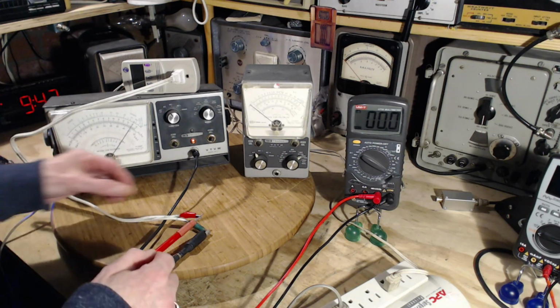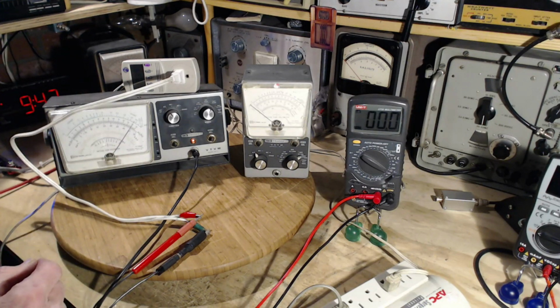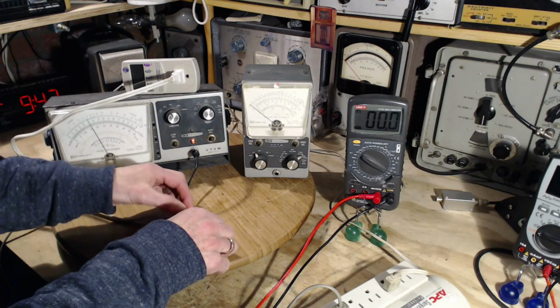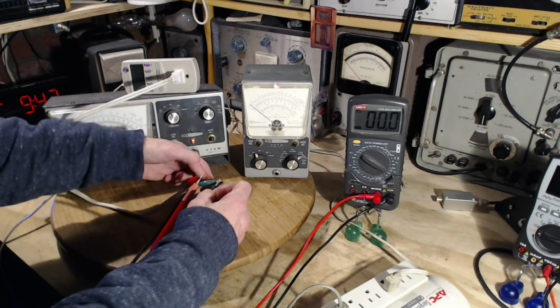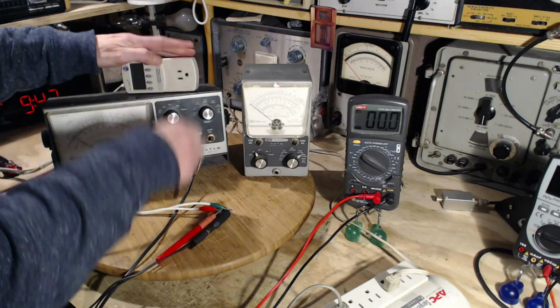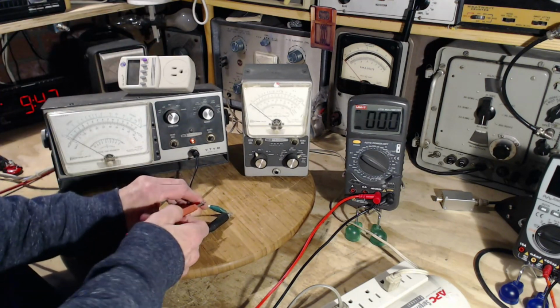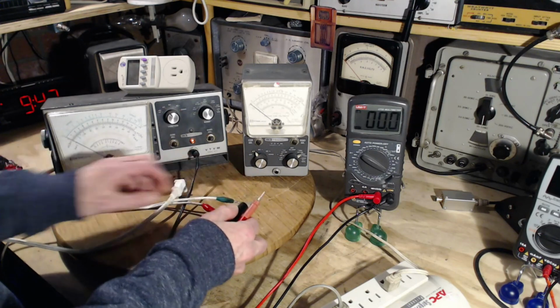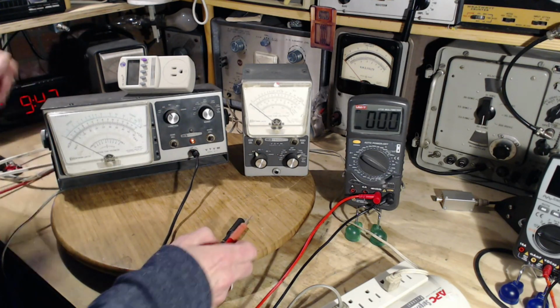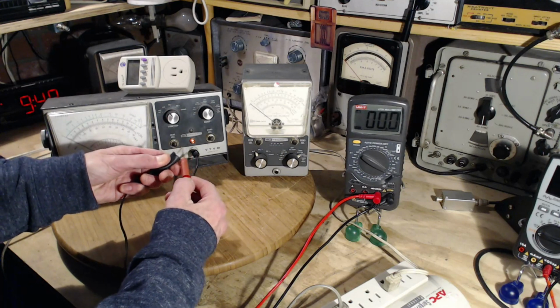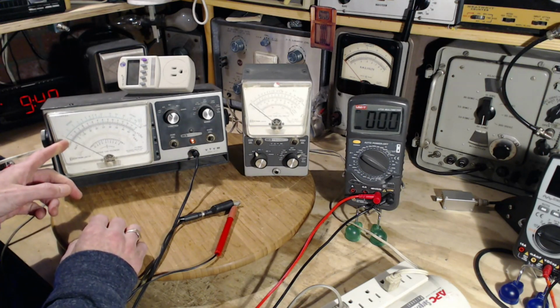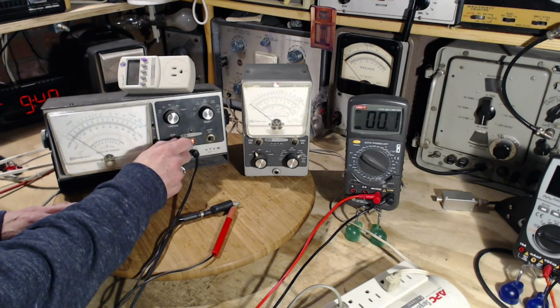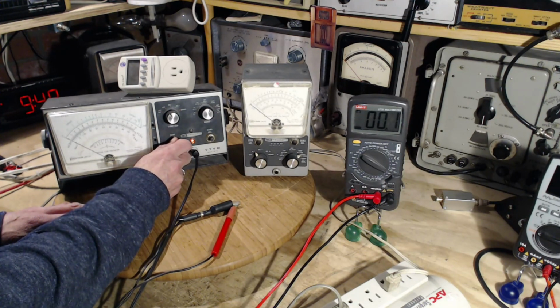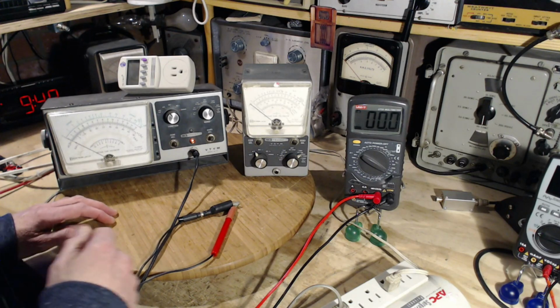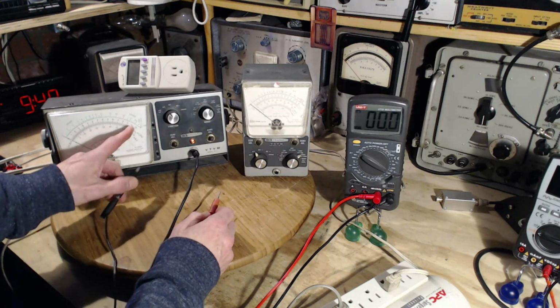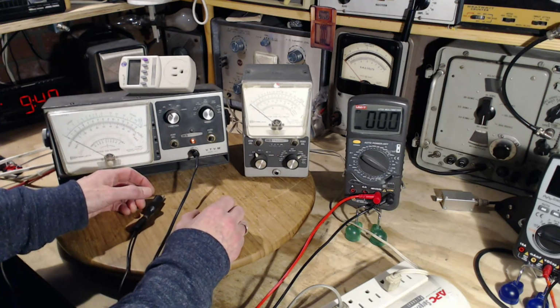Now let's check a couple things here. Before I get myself a shock, shut that off. Separate these. Let's do this. That makes me feel much better. Okay. Short these together. Checking the zero. Zero adjust. Is it? Yeah, it does have an effect. Even in AC, it's definitely on zero. That's all I needed to do. So we're really getting a wrong reading of 140 on there.